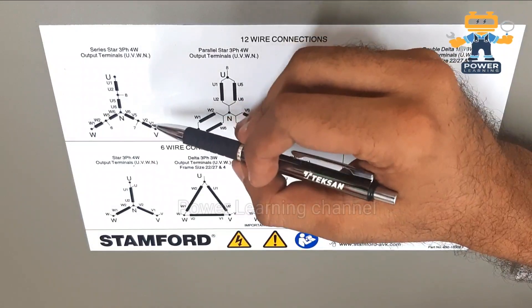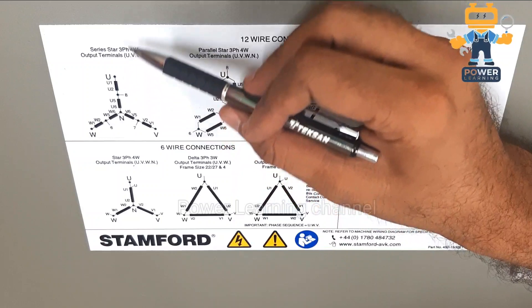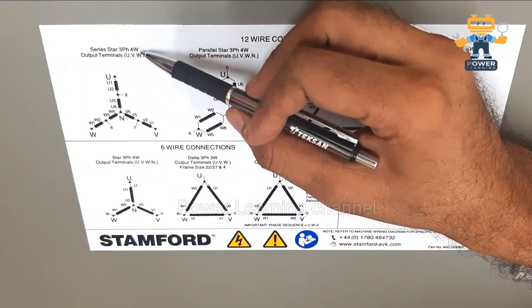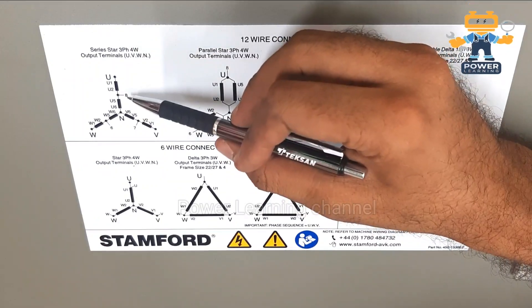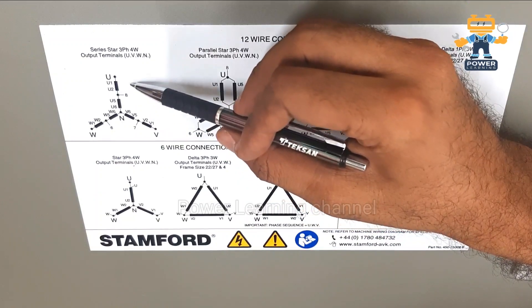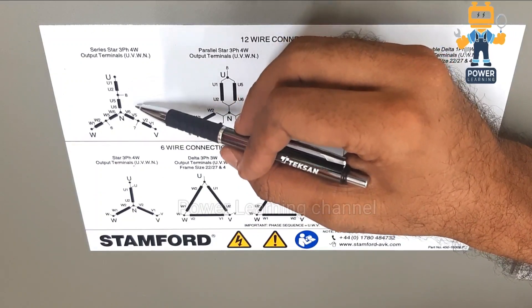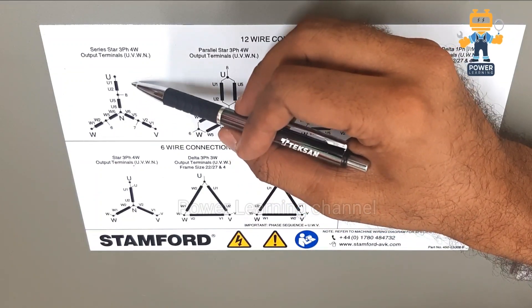In the standard configuration we use series star — a three-phase four-wire system — producing 380 volts line to line and 220 volts line to neutral.